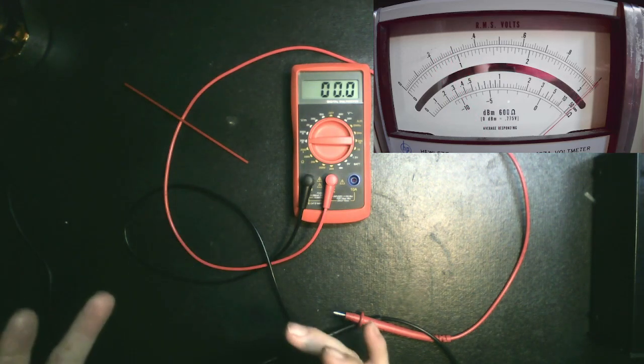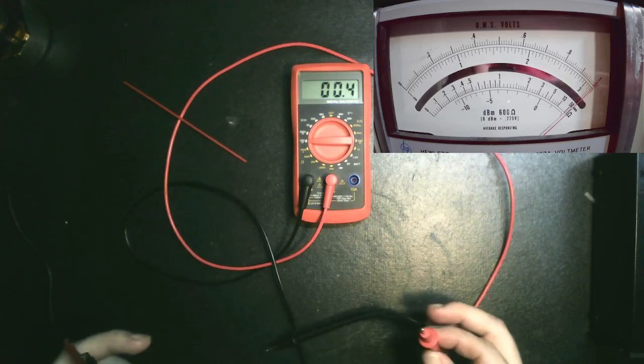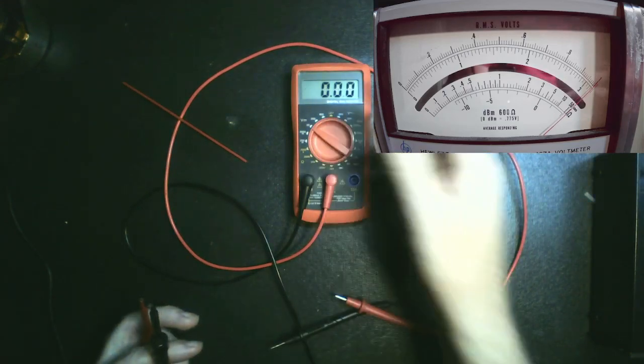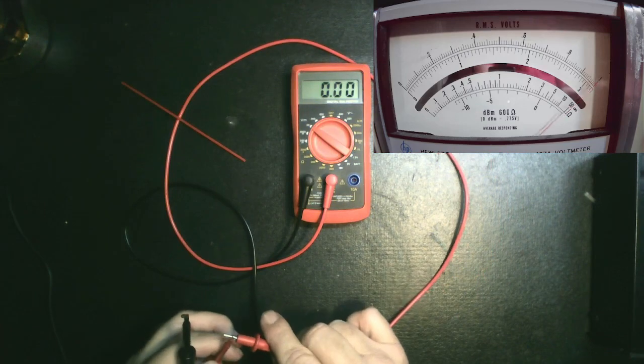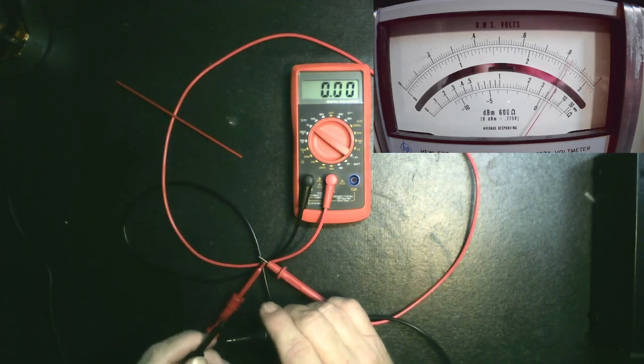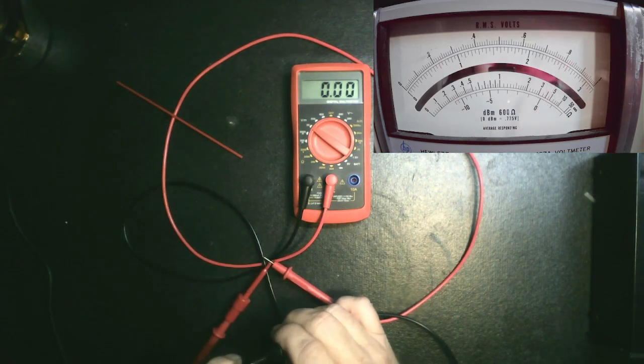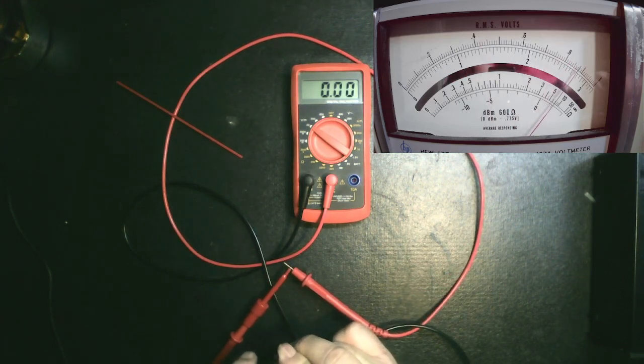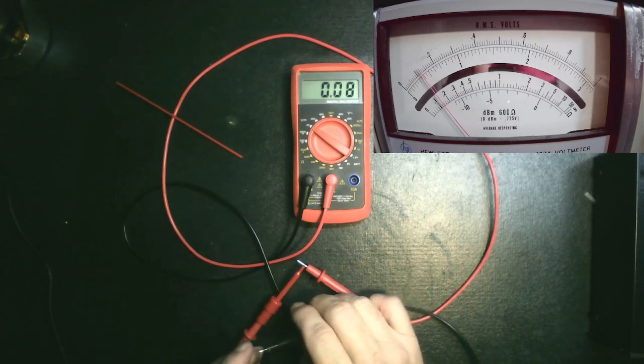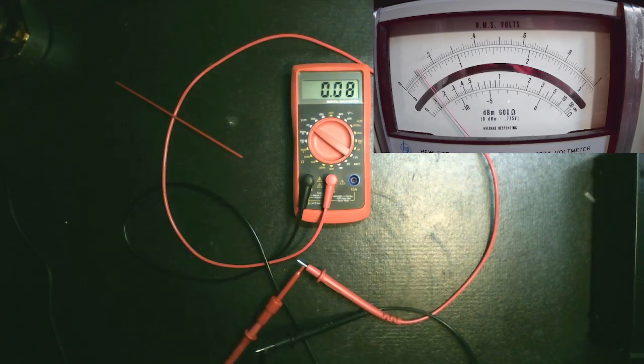So I want to put these on here because I want to clip them to the leads here. And you'll see it's not going to matter where I'm at on that. So I go ahead and clip it there. I clip it there. Whoops. And I clip it there, and it drops way down. So let's go ahead and drop our reading here. Now I'm in the times 1 mega ohm. So I take my reading on the screen, which is just about 1. Multiply it times 1, we get 1 mega ohm.